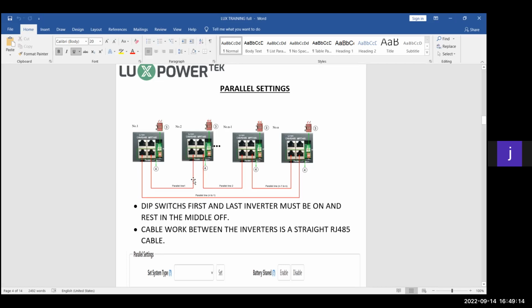So the main thing that you must remember out of your parallel system is the configuration of your cables between the machines. It's very important that you know of the parallel ports. They're marked parallel ports. The first parallel port is connected to the last parallel port of the inverter. If there's 2 inverters, it will go from the first one all the way to the last one. Then the parallel ports in the middle will be connected like this. That's if there was 2 inverters. If there's 3 inverters, the configuration stays the same. The first one goes to the last inverter, and then it just daisy chains through the inverters. Then from there, if there's 4, everything stays the same.